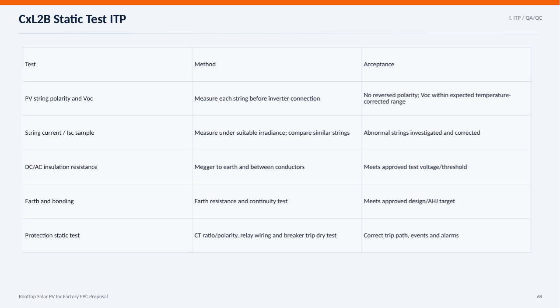Next, we sample the string current under proper irradiance and compare it across similar strings to identify any abnormalities that need correction. We also perform insulation resistance tests using a megger, verifying that the DC and AC insulation meet the approved voltage and resistance thresholds. Additionally, earth resistance and continuity tests confirm proper grounding according to design and authority having jurisdiction targets. Finally, the protection static tests cover current transformer ratios and polarity, relay wiring, and breaker trip functions to ensure correct trip paths and alarm events. This thorough testing is crucial for a safe and efficient solar PV installation.